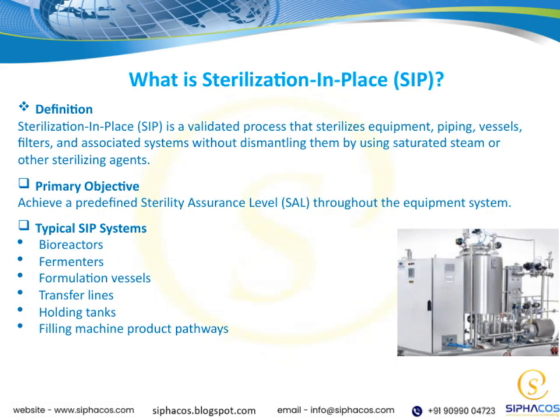Let's talk about sterilization in place, or SIP. It's a carefully validated process that sterilizes equipment and systems without taking them apart. Instead, it uses saturated steam or other agents to kill any contaminants inside. The main goal here is to reach a specific sterility assurance level, making sure everything is reliably sterile throughout the entire system. You'll find SIP used in places like bioreactors, fermenters, formulation vessels, transfer lines, holding tanks, and even the product pathways in filling machines. It's all about keeping things clean, efficient, and safe.